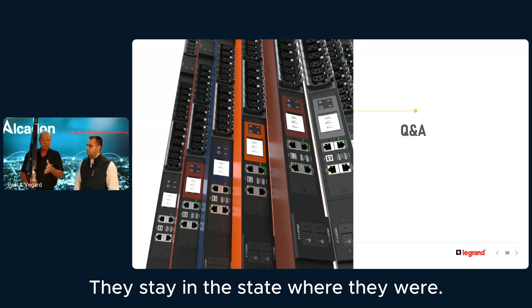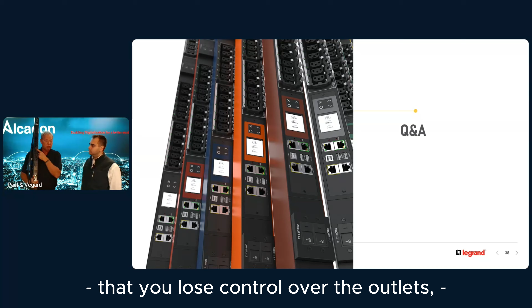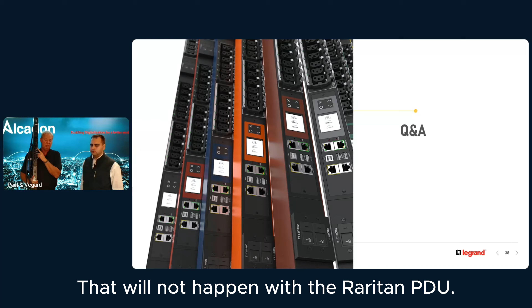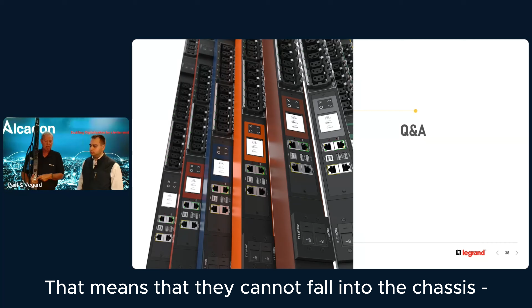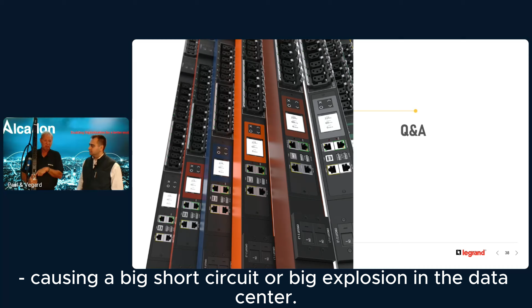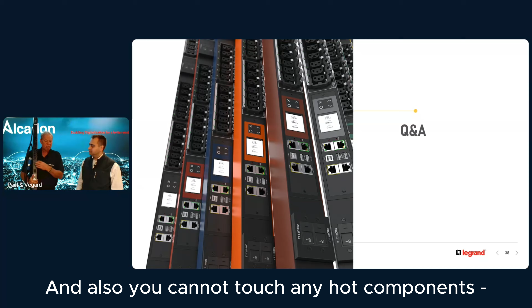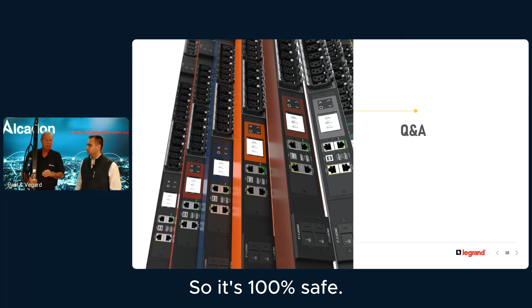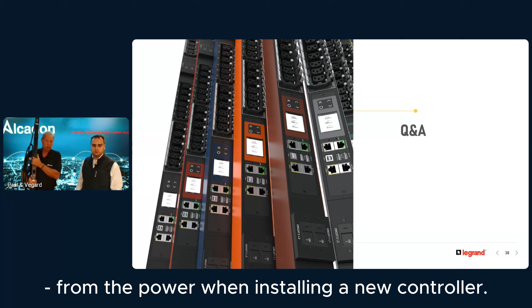They stay in the state they were in - if an outlet was on, it stays on, and if it was off, it stays off. With competitors, when you remove the controller you lose control over the outlets and all of them switch off - that will not happen with a Raritan PDU. Also, the screws are finger-safe, meaning they cannot fall into the chassis causing a short circuit or explosion in the data center. You cannot touch any hot components when removing the controller, so it's 100% safe, and there's no need to disconnect the PDU from power when installing a new controller.